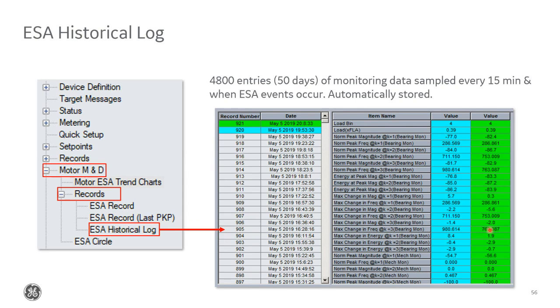Another record that we provide is the historical log. This log stores up to 4,800 entries or 50 days worth of data. Every 15 minutes or when an event occurs, the relay will store a snapshot of all the values we looked at to this log. You can find this log in the same menu as before under ESA historical log. And you can also download this file in CSV format so you can plot it in another table if you'd like. And also when you connect to the relay using the setup software, the software does automatically pull and back up this entire file to your computer. The file is automatically saved to a predefined GE directory on your PC.